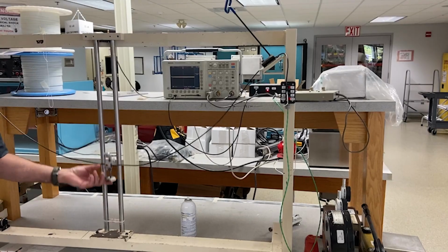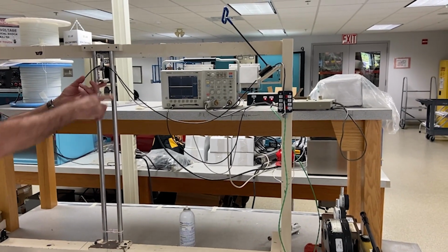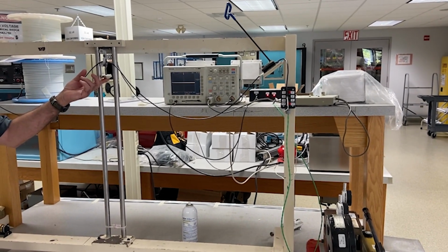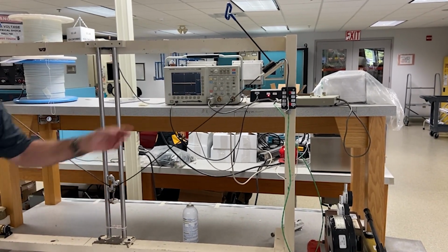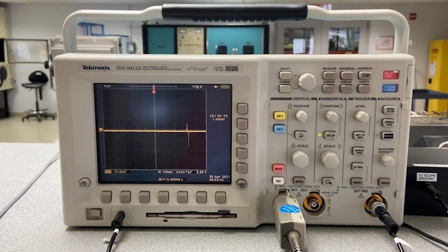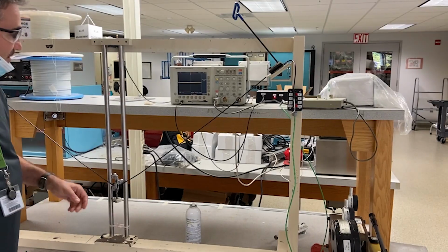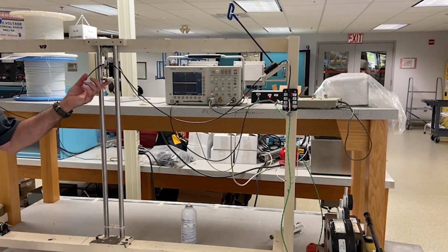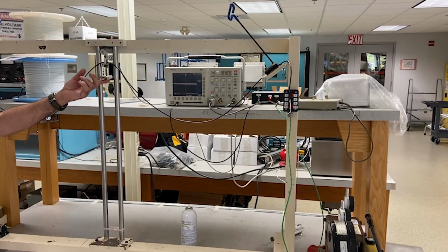So how do we test for low noise here at New England Wire? Well, we use standard ANSI AAMI EC53, which has a test method in there that allows for testing for triboelectric noise. Basically, we take a section of cable that is suspended by two posts. In the middle of that, you have a weight. One end is connected to an oscilloscope. So you drop the weight, that creates a shock, which creates some noise, which is recorded on the oscilloscope. And that's basically what we get for results for triboelectric noise.